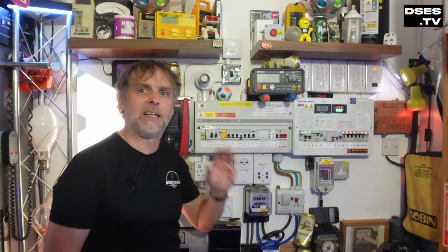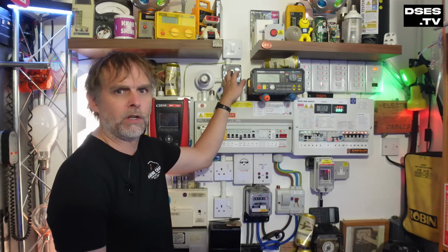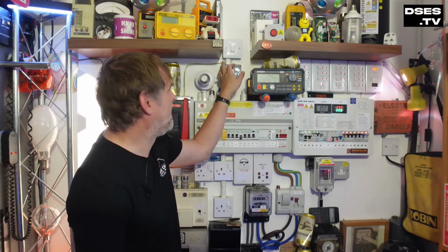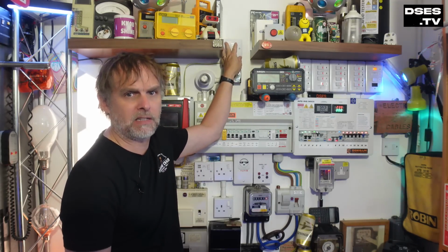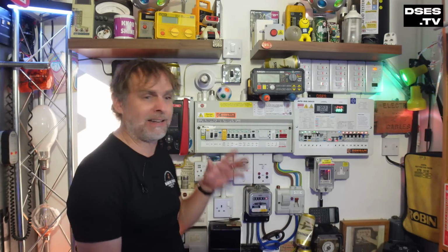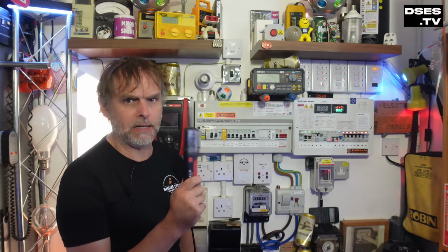If I were to open up both of these switches, I would physically see a circuit protective conductor installed on each. One goes to the metalwork of this decorative plate, the other to the metal back box that the screws of this plastic faceplate attach to. Surely both protective conductors go back to the main earthing terminal, no? Well, no, obviously not if there's a potential difference between them. One of them is earthed back to the MET, the other, as I said, is floating. Which is which? Well, that's reason number 1.5 for using a dedicated voltage tester.